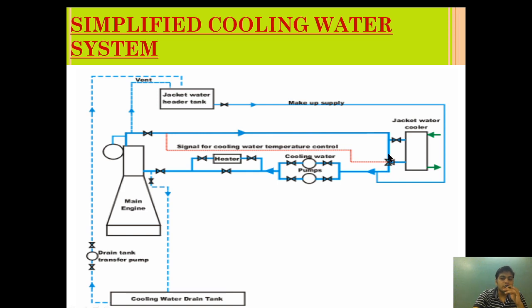While returning back to the cooler, a three-way valve is provided which decides the amount of cooling required for the jacket water cooler. In the three-way valve, it mixes the cooled jacket water and the heated jacket water such that the inlet temperature of the jacket water is maintained at 68 to 70 degrees Celsius. The amount of mixing is controlled by throttling the valve of the water coming out from the jacket and the water coming out from the cooler, by taking the temperature reading from the outlet of the jacket. The inlet temperature is around 68 to 70 degrees Celsius and the outlet temperature is 78 to 82 degrees Celsius.